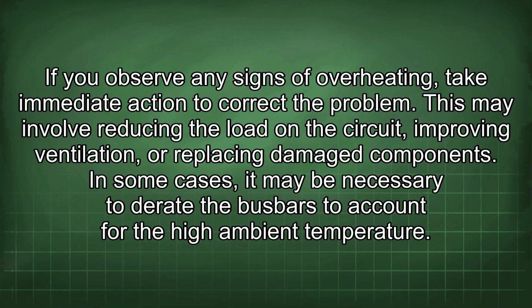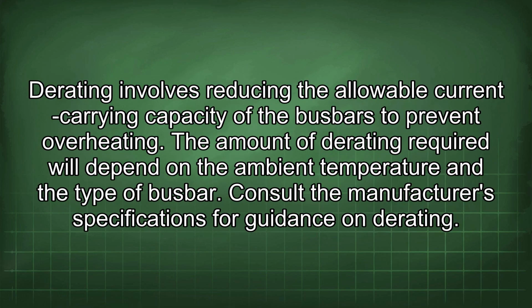In some cases, it may be necessary to derate the busbars to account for the high ambient temperature. Derating involves reducing the allowable current carrying capacity of the busbars to prevent overheating. The amount of derating required will depend on the ambient temperature and the type of busbar. Consult the manufacturer's specifications for guidance on derating.